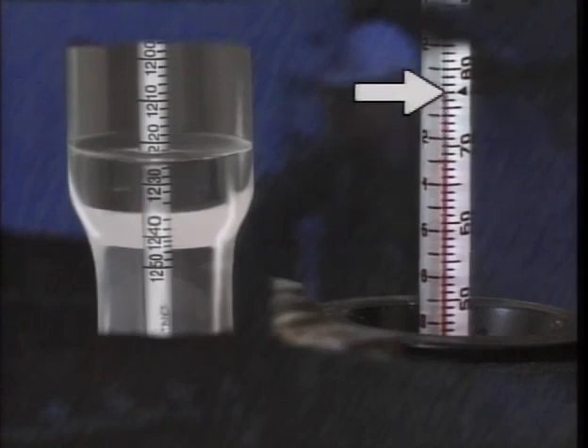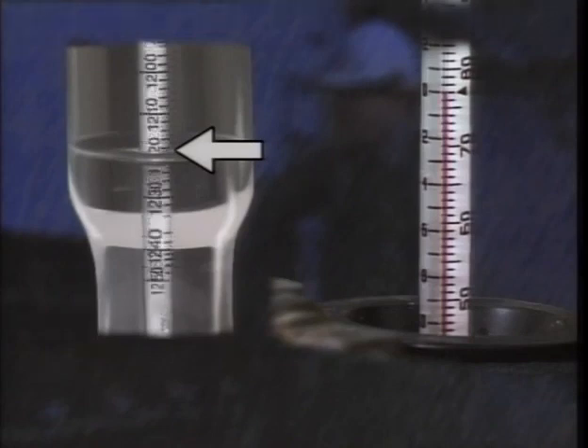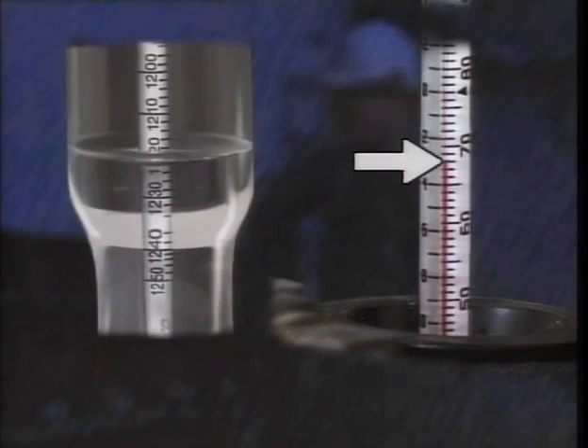When electrolyte temperature increases, its specific gravity decreases because warmer liquids are less dense than cooler liquids. When the temperature decreases, the specific gravity increases.